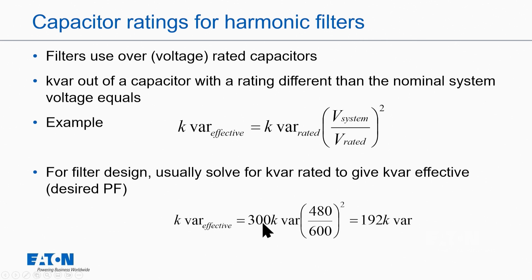So if I have, for example, a 300 kvar capacitor, I'm only going to get 192 kvar out of that capacitor if I apply at 480 if it's a 600 volt rated cap. So you could say, well, I'm just going to oversize the cap like I would a K rated transformer. But in this case, when I oversize it, what I'm actually doing is reducing the amount of kvar associated with it.